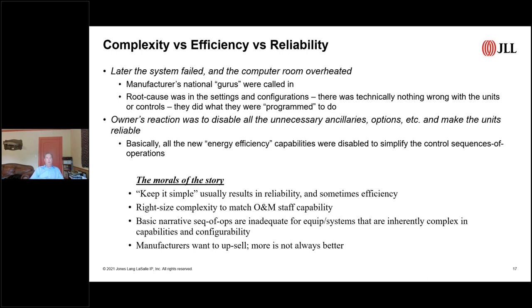Several months later, I got a phone call that the system had failed and the computer room had overheated. They wanted to know what happened and why it passed commissioning yet failed in operation. So I ended up calling in the manufacturer's national gurus, the people who actually wrote the programming and manuals for this equipment. They did a root cause analysis, checked everything out, and basically said the units were perfectly fine - they did exactly what they were programmed to do. They were just set up and programmed incorrectly.